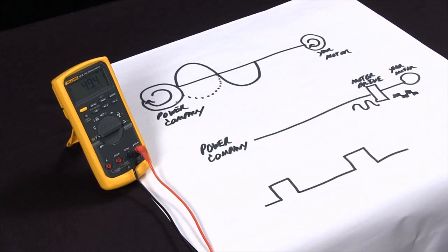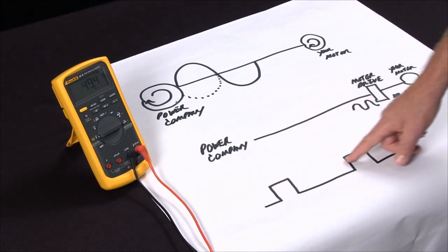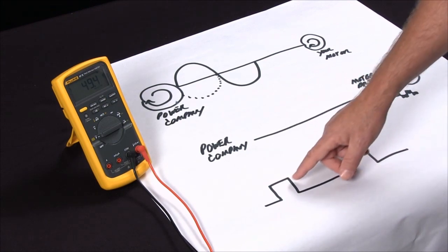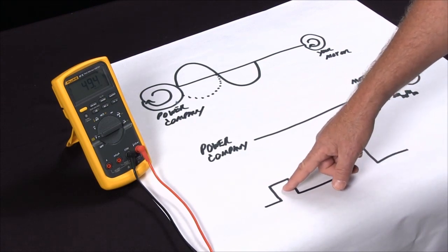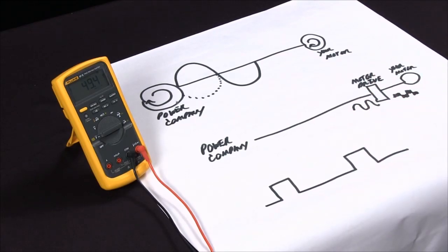By simply doing the duty cycle measurement, I can see if the waveform is symmetrical. This is very handy if you're looking at an encoder where you have a square wave. You'd like to see the pulse maybe 50 percent on, 50 percent off for a properly set encoder motor.